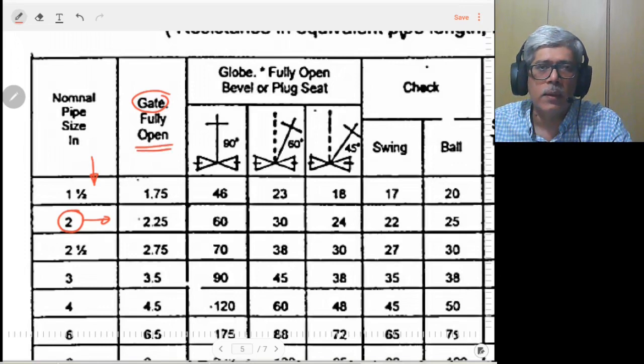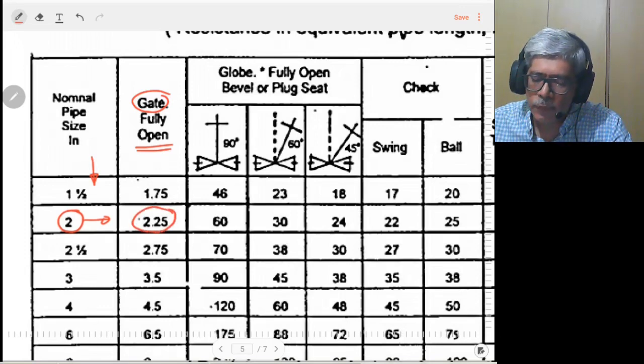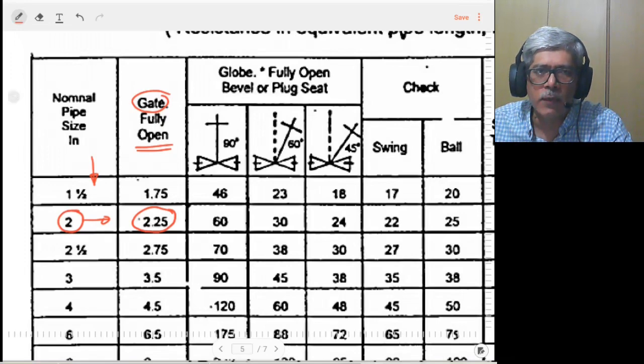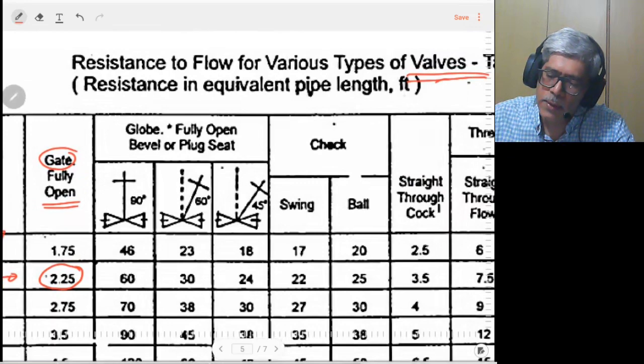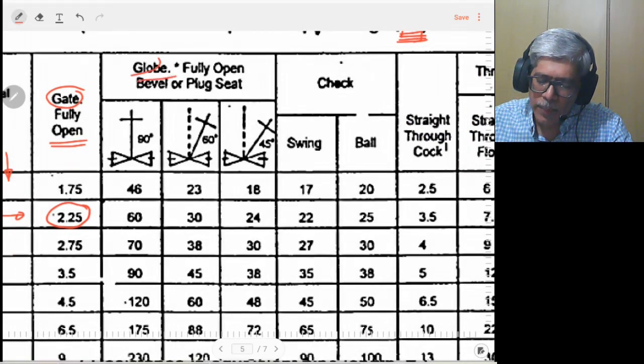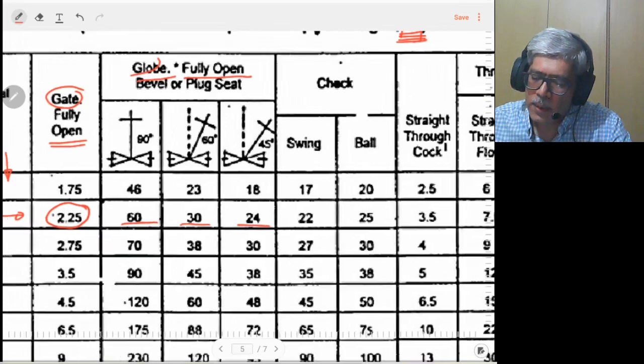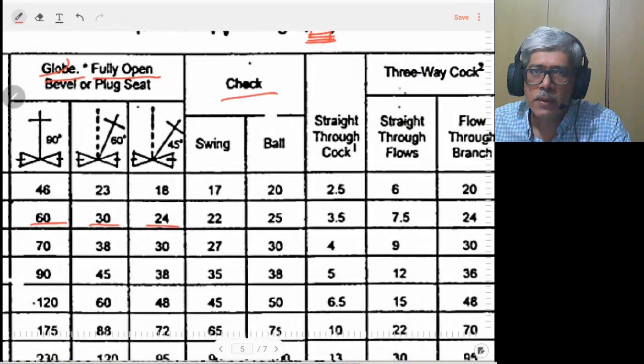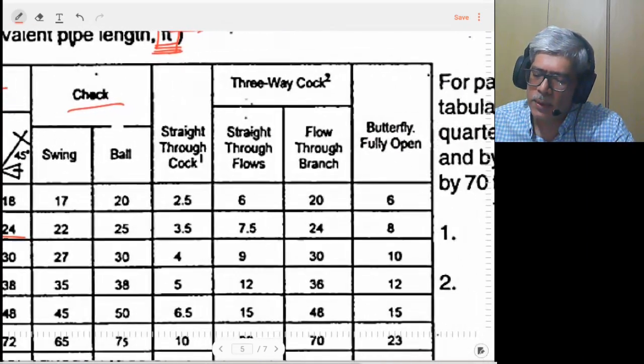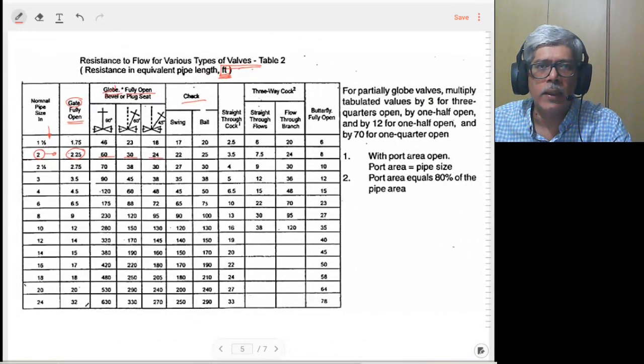A gate valve of two-inch size is equivalent to a pipe which is 2.25 feet. This particular table uses FPS units, so the unit of equivalent pipe length is given in feet. Similarly, for globe valves, depending on their condition and the orientation of the handle, there are different lengths available. For check valves and other types of valves, the values are also given. In this way, if your pipeline has got valves, they can be converted into an equivalent straight length.